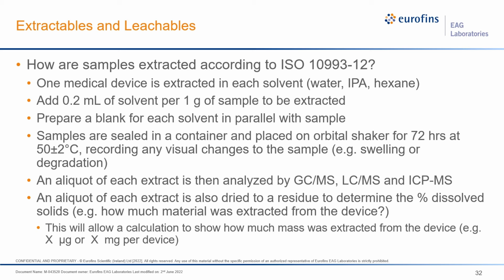We'll get our samples ready to go, and then we'll heat them for 72 hours at 50 degrees C, and we'll note any visual changes such as degradation or swelling. We'll then take an aliquot of all of those fractions and analyze them by the appropriate techniques. We'll also take a little bit of that solvent and dry it down to a residue to see what the total percent dissolved solids is, so we can calculate how many milligrams or micrograms of material could be extracted from this medical device.